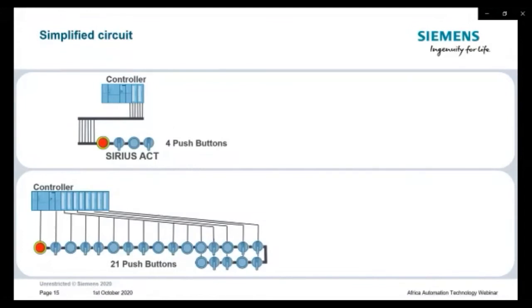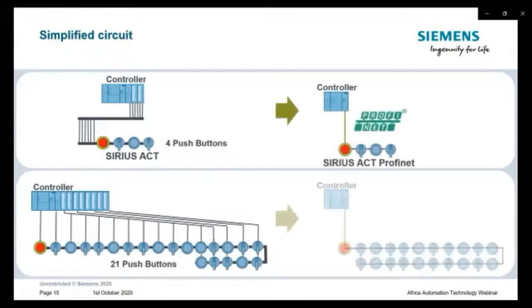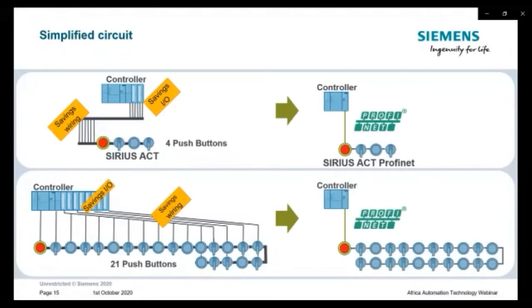The saving benefits are not only limited to installation time and wiring. The saving benefits include high cost saving potentials. You see the difference on the left side compared to the right side. That's space saving advantages and wiring advantages. You only need the controller and the PROFINET cable here on the right side. In addition, the installation with SIRIUS ACT and SIMATIC allows an integration into the TIA Portal we have seen in the video. And this enables easy commissioning and maintenance advantages, further to the already mentioned saving potential.